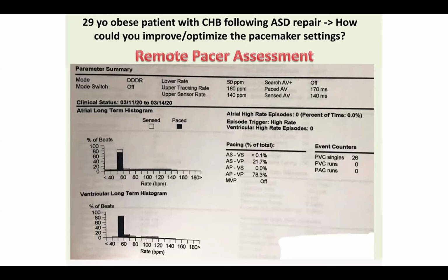Remember, rate responsiveness means that the device has some sort of a sensor in it that determines activity, just as you said. And as the activity increases, the device will slowly raise the lower rate limit of the device. So when it says the lower rate is 50, you're basically telling the pacemaker, never let the patient's heart rate go below 50. However, because the R feature is on, the fourth letter is on, the device will slowly increase the lower rate limit up to the upper sensor rate, which is 140.